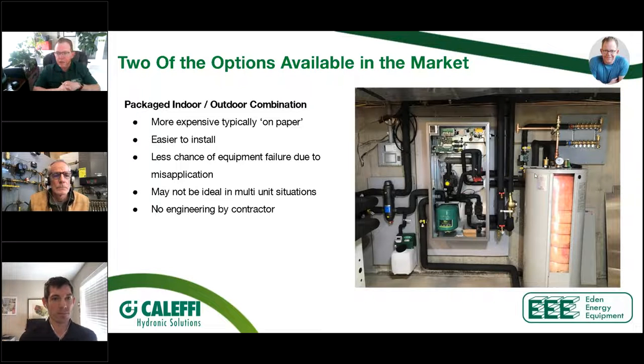What I really like about this, and I say this with full respect to everybody, is this equipment does not require engineering by the contractor. No good contractors want to be engineers or pretend to be, any more than engineers want to pretend to be contractors. So the picture that we have here is actually the installation in John Siegenthaler's place. So this is a pretty simple installation. It has a TurboMax installed here on the right-hand side that's taking care of the domestic hot water. And then we can actually see where the heating loads are going out to the building to take care of heating as well as cooling options throughout.